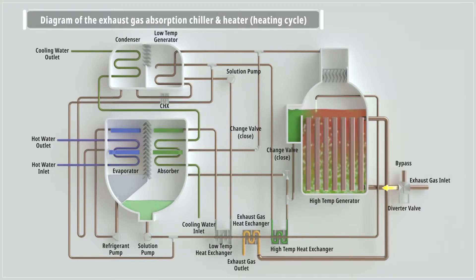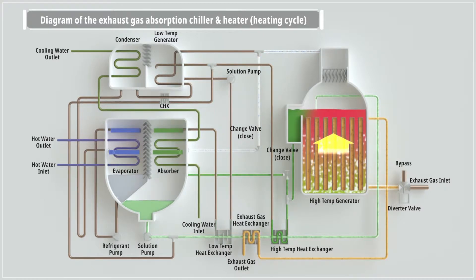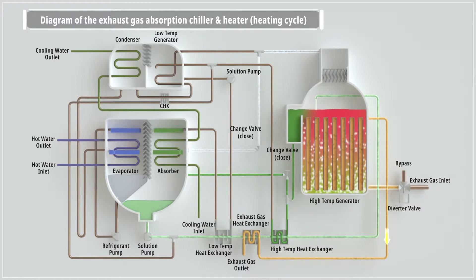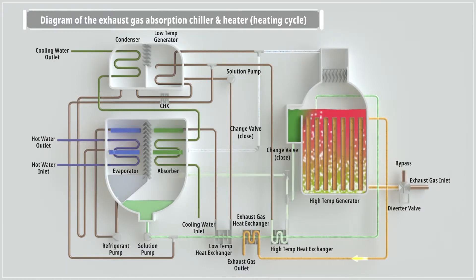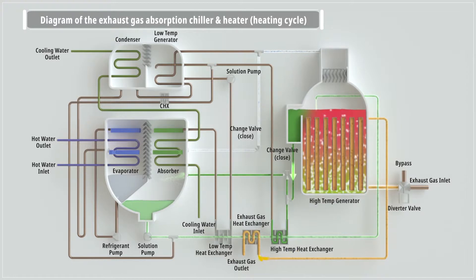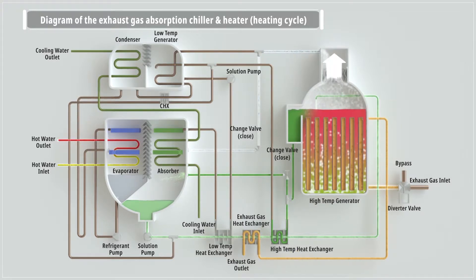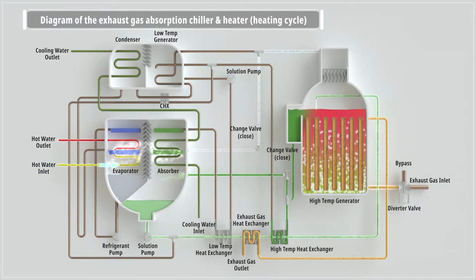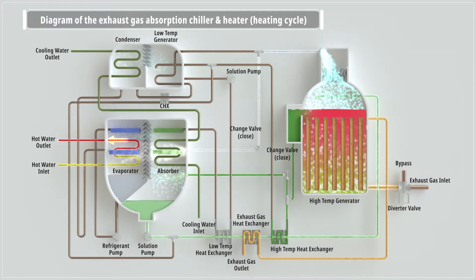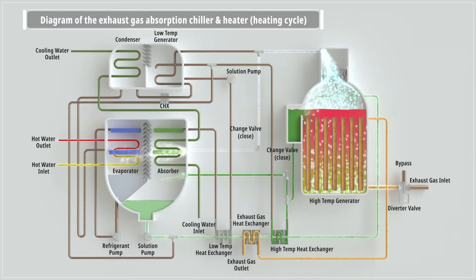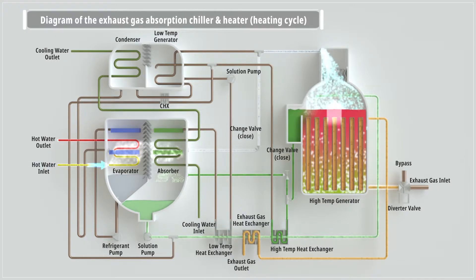CHP system's heating works in simpler logistics. Heated by incoming exhaust gas in the high temperature generator, the solution releases refrigerant into vapor, becoming a concentrated solution which flows to the absorber. High temperature vapor flows to the evaporator, heating up incoming hot water. The vapor, condensed to liquid by releasing heat, is then mixed into the solution in the absorber, flowing back to the high temperature generator and repeating the cycle.